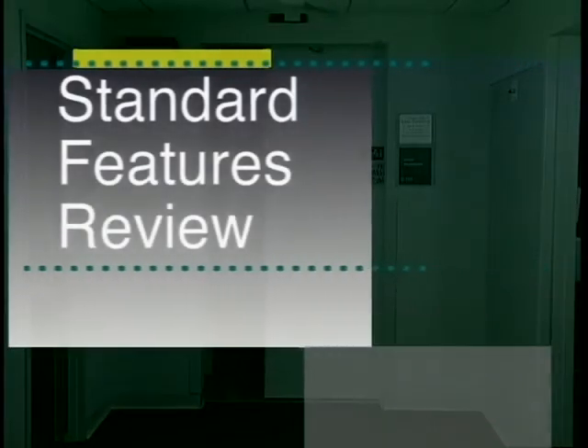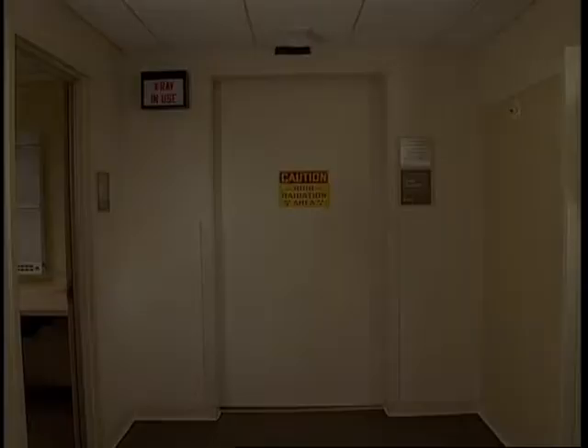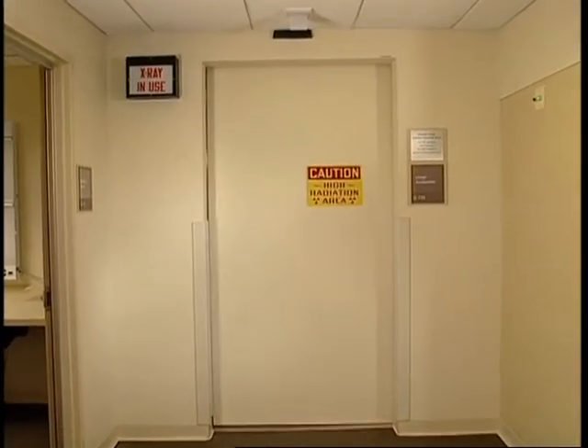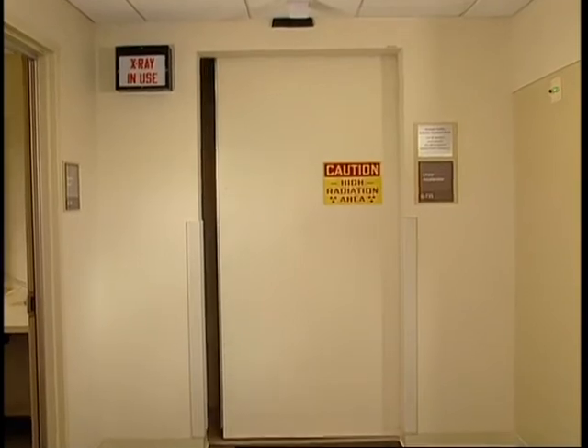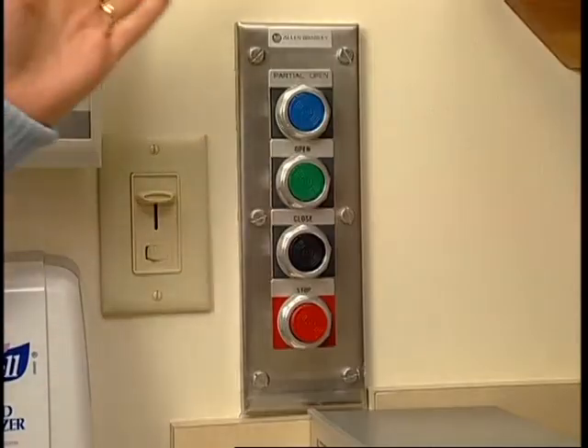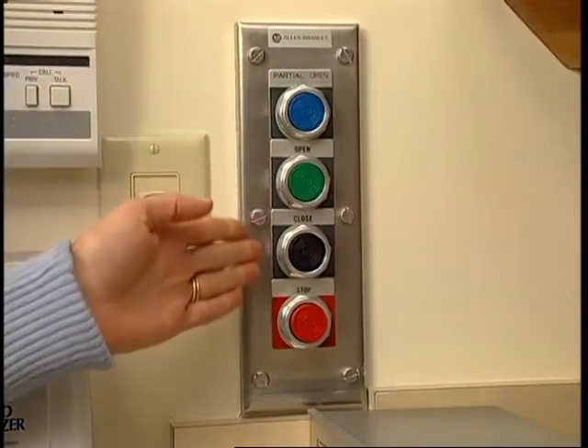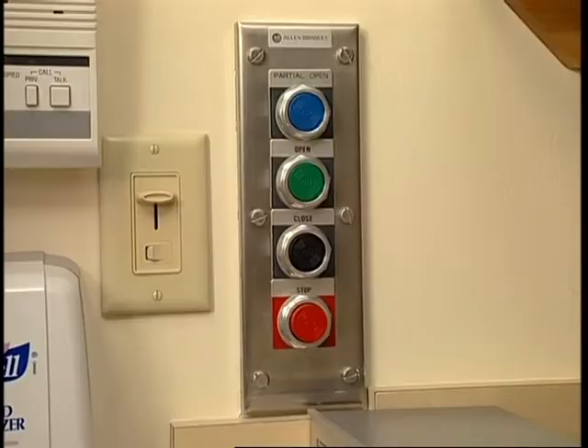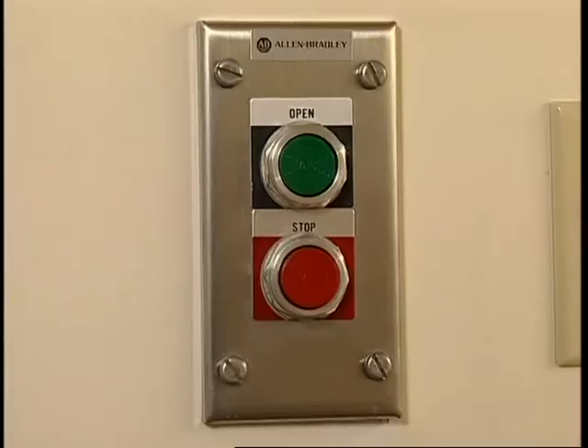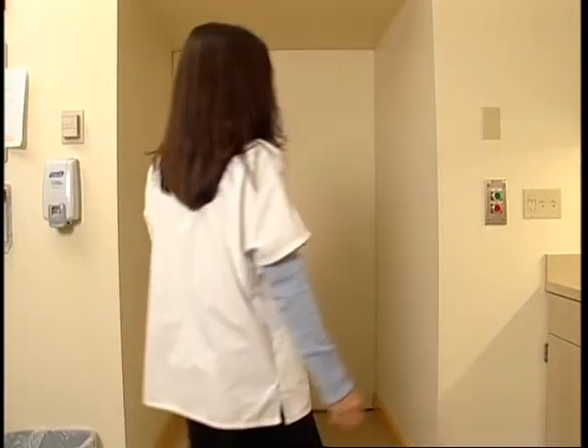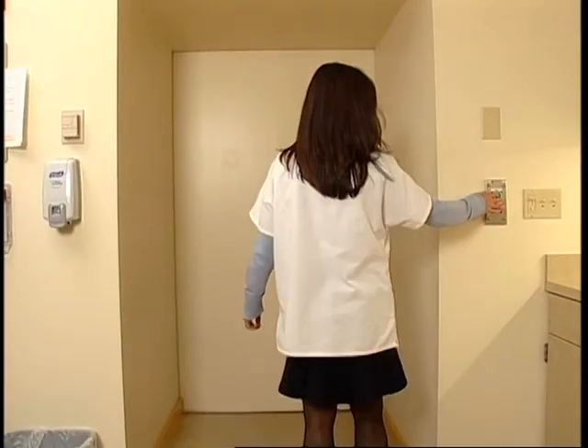First, we'll review the door's standard features. The NELCO sliding door system is operated by two sets of switches: a four-button group located on the exterior of the room, and a two-button group mounted on the interior of the linac room.